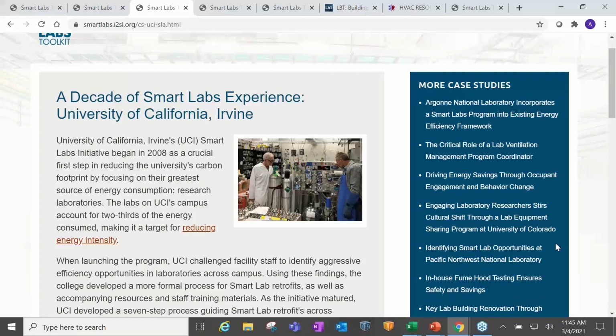Great question. And the best way is local exhaust. So you can put a snorkel or a high-tech version of a snorkel right by the soldering station. Could be a very small capture hood. So get the exhaust as close to the process as possible. We always want to contain the process and not let it get out. But a canopy doesn't do that, and it ends up also drawing a whole lot of air, and often draws it right by the user. So it's not an effective approach.